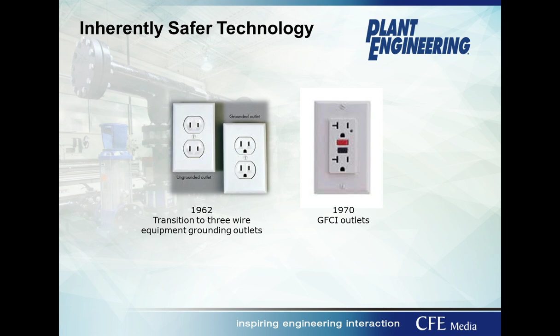Today, we have other technology that looks at different hazards, such as the arc fault circuit interrupter outlets and breakers. So again, these are representative of the evolution. If you look hard, in some organizations and facilities, you will find opportunities to improve the equipment grounding protection, either through the three-wire grounded outlets or the GFCI outlets. There are still opportunities in older facilities to do that. The code doesn't require it. OSHA does not require that you update to meet the current code, but the opportunity is there if you see that you have risk that you want to reduce.